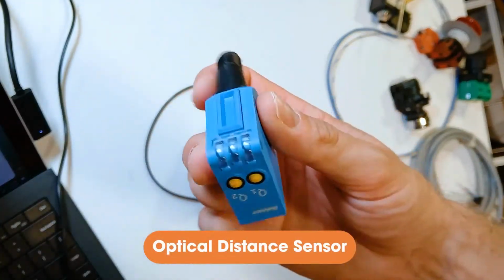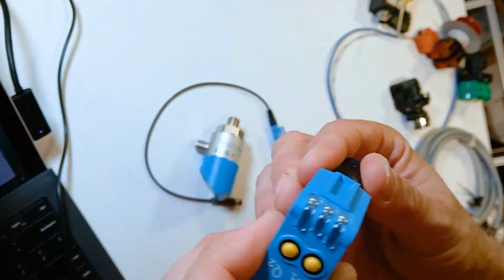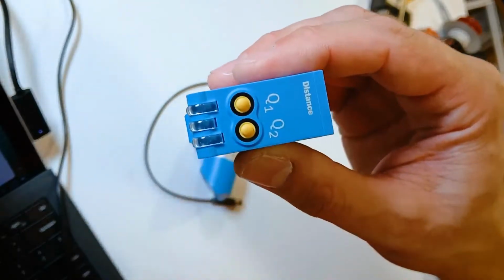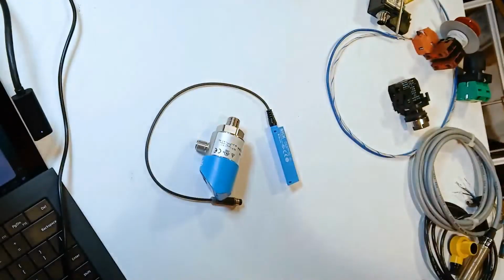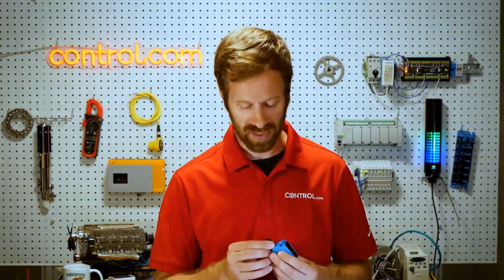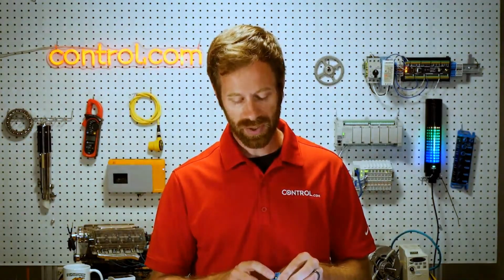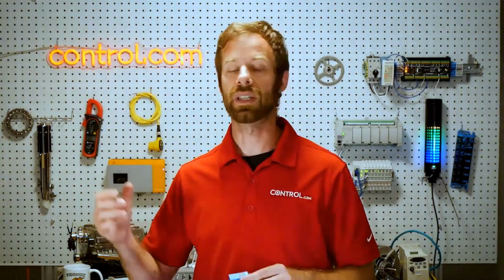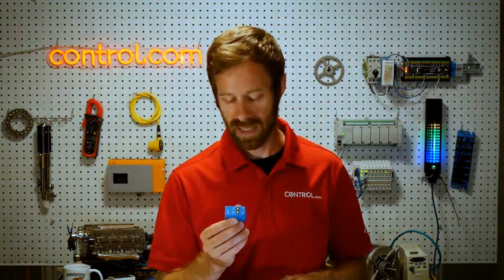It will return back my distance as an integer. And I also see on the top these notations for Q1 and Q2. Not only can I set these and allow the sensor to act as a discrete sensor with 2 output set points, that's pretty cool, but I can also use those 2 individual set points as part of my I/O link data package, creating a sensor that can send a lot of different signals depending on how we want to use it.